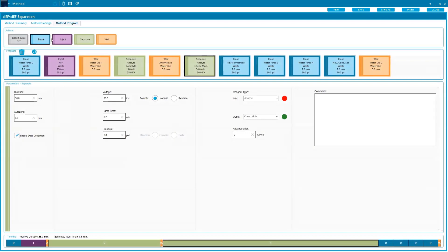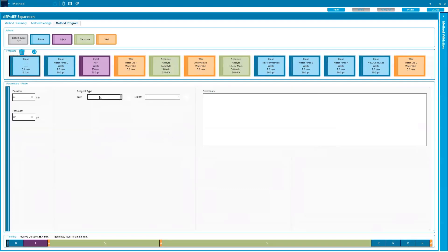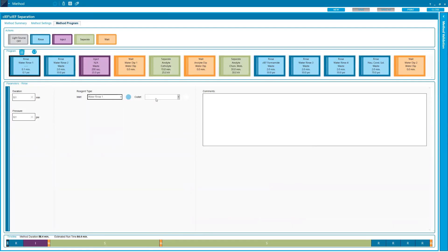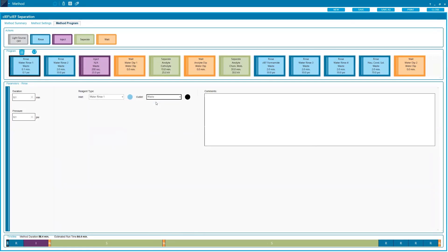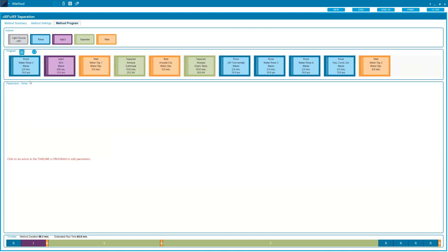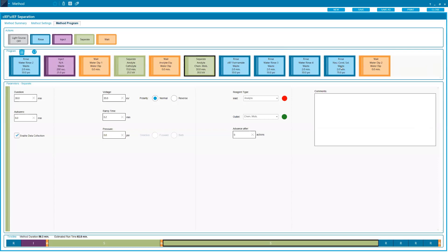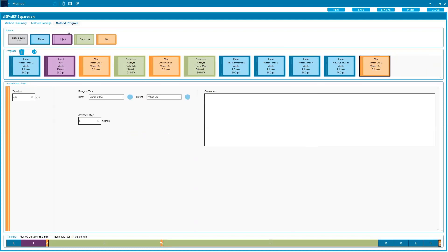You can also see the loaded reagents here from our reagent set that we had made. If we go to our method program, you can see all of our actions here also color coded. This is just a drag and drop system. We want to add a rinse here, we just drag it down. Then we choose from our reagent types what we want to do. Maybe we want to just start with the water rinse going into waste. It's not going from one static location to another, but this is fully dynamic. Here you just choose your duration, say pressure, or if we didn't want it, we can just drag that to the trash can. We have a water rinse, injection, waits for our water dips, separation, and our remobilization step. And then afterwards, we have a few different rinse steps to remove all of the sample from our capillary prior to the next injection.